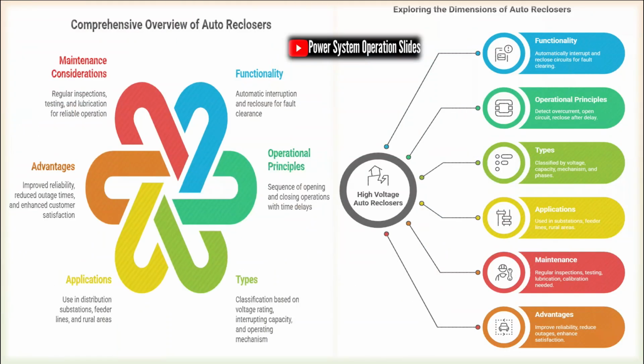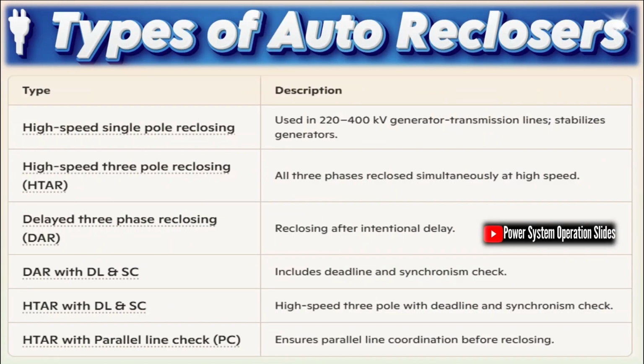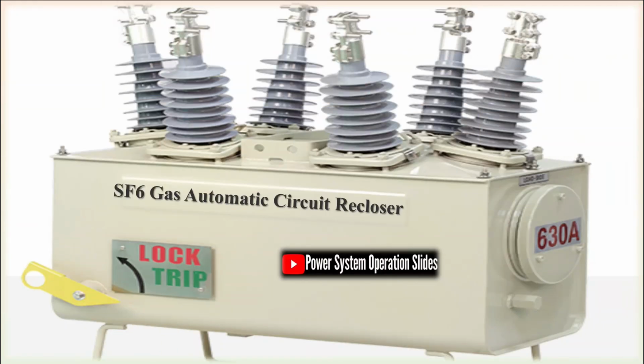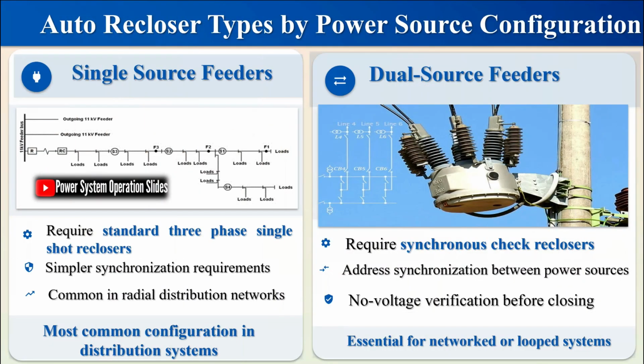How auto reclosers work. Basic principles. The working principle of auto reclosers is based on their intelligent management and restoration capabilities within power lines. Their core function cleverly utilizes the transient nature of power line faults. 1. Fault detection. When a line experiences a transient fault, e.g., due to a lightning strike or foreign objects blown by wind, the protective relaying system immediately issues a command to quickly cut off power, causing the circuit breaker to trip and isolate the fault.